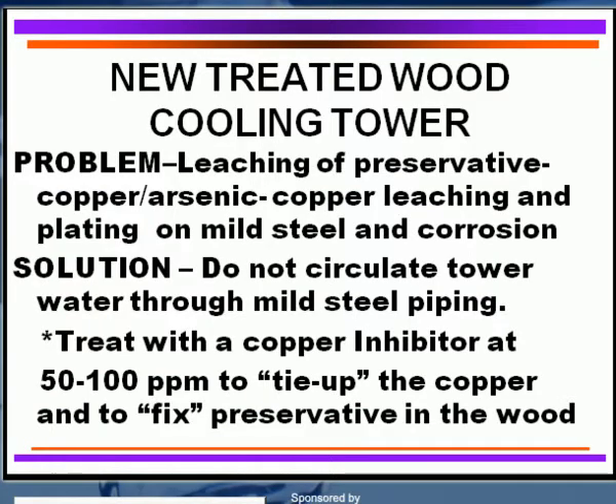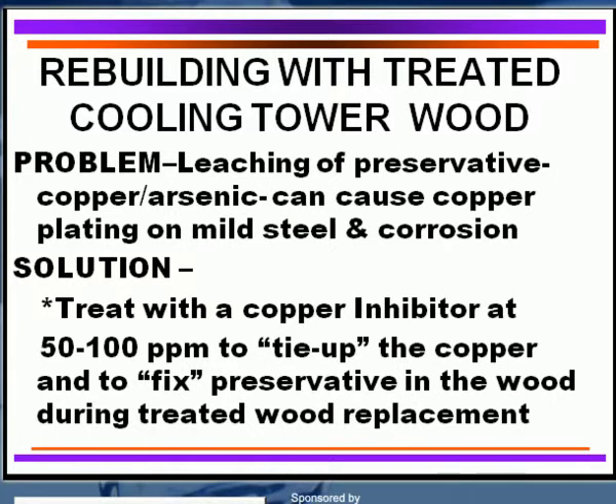Now, if you're rebuilding a cooling tower with treated redwood, again, or treated Douglas fir, the leaching of the preservative, again, can cause a serious copper plating problem. Well, if the water's actually going on continuously, many people will treat it with a copper inhibitor with a shot of 50 to 100 ppm to tie up that copper and fix that preservative.